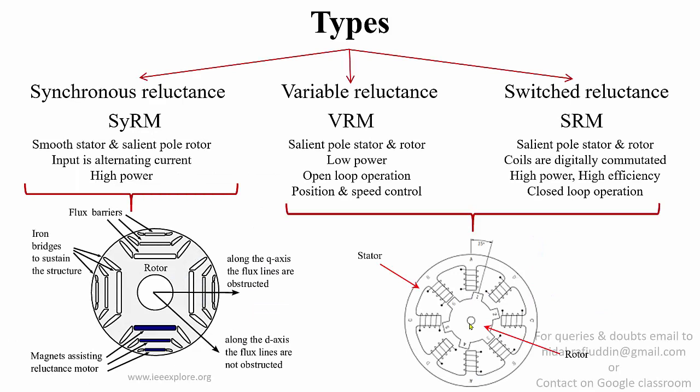Reluctance motors are of three types: synchronous reluctance, variable reluctance, and switched reluctance, abbreviated as SYRM, VRM, and SRM respectively. Each of these has different operating applications. The synchronous reluctance motor has a salient rotor and a smooth stator similar to an induction motor, while both the variable reluctance motor and the switched reluctance motor have salient pole rotors and stators. The synchronous reluctance motor takes AC input and is available at high power ratings. The variable reluctance motor has a low power rating and operates in open loop with no feedback. In the switched reluctance motor, the stator coils are digitally commutated and operation is controlled by a closed-loop feedback system.